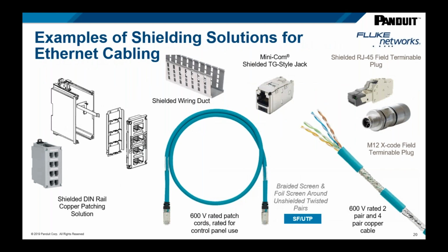A quick look at some of those shielding components and the range that you can find available for a control panel application. We're going to talk about patch panels. There are shielded patch panels out there. 600 volt rated shielded cabling is becoming very common in the control panel. We're showing you an example there. It is an SFUTP cable. That's in a patch form. It's also available in a cable form in 2 and 4 pair variations. And then you'll have your shielded connectors that are part of that system as well. There are also things like shielded wiring duct that provide an additional layer of protection from noise-producing sources. These are sometimes used in a retrofit situation where you run into a noise problem and you need a way to mitigate it. Something like a shielded wiring duct is an easy one to implement.